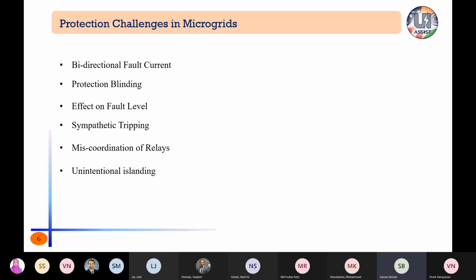So naturally, for the relays located upstream on the feeder, the current sensed by those relays reduces. So it may happen that the relay in the upstream position does not find the current to be a fault current as such. In that case, it remains blind to that fault. So this type of problem arises, that is protection blinding. And also fault level increases. This happens when we have a distribution network or microgrid and suppose one DG is placed at some bus. Then downstream of the DG, the fault level will increase because of DG penetration. So naturally the circuit breaker capacity needs to be modified or changed because of DG penetration.